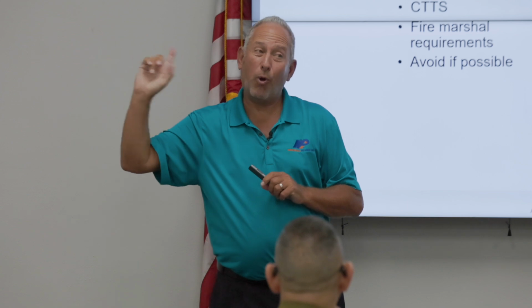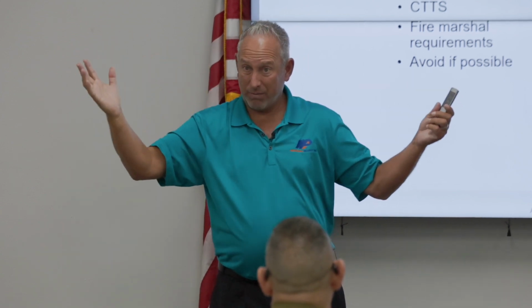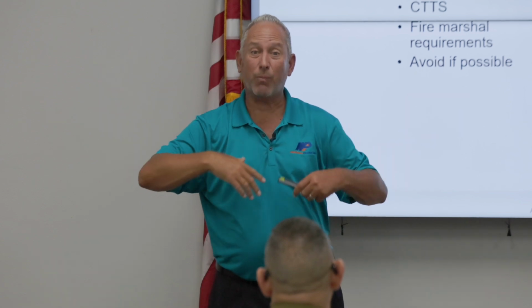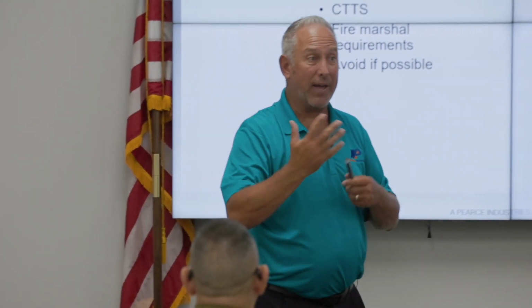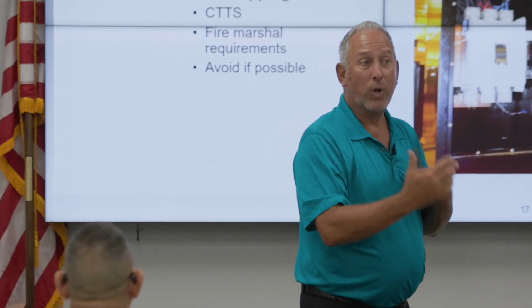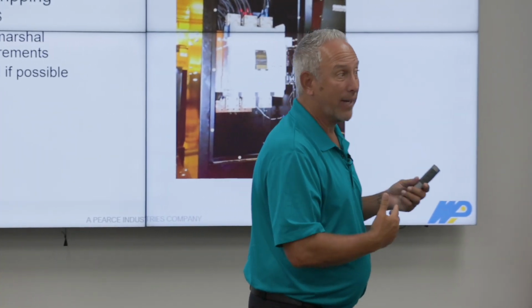Now, other people go, no, don't trip the breaker in the generator. I want to keep power on so we can do whatever. We can do smoke evacuation, we can do whatever may be. So you have that conversation in the beginning going, what do you want the generator to do in those kinds of events?